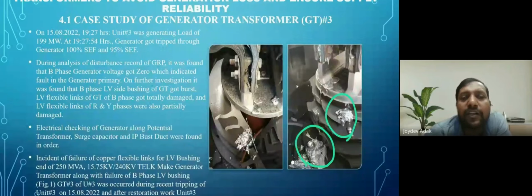So this LV bushing burst due to improper monitoring of the system, transformer bushing, and also the stator. This is case one, that is the failure in the transformer bushing. This is the generator transformer bushing. Due to this failure, it tripped the unit instantly, and the interruption was there for a long time. If any fault occurs in the GT, there is no option other than interruption. The restoration period may go from 7 days to 1 month or 1 year. So that is the non-availability of the unit.